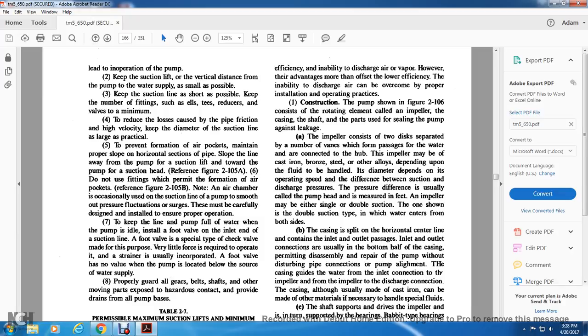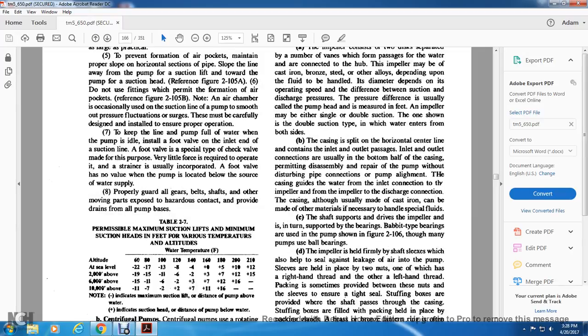The difference between the suction and discharge pressure of the pump is usually called the pump head, measured in feet. The impeller may be either single or double suction. The one shown is the double suction type, in which water enters from both sides. The casing is split on the horizontal center line and contains the inlet and outlet passages. Inlet and outlet connections are usually on the bottom half of the casing, permitting disassembly and repair of the pump without disturbing the pipe connections. The casing guides the water from the inlet connection to the impeller, and from the impeller to the discharge connection.